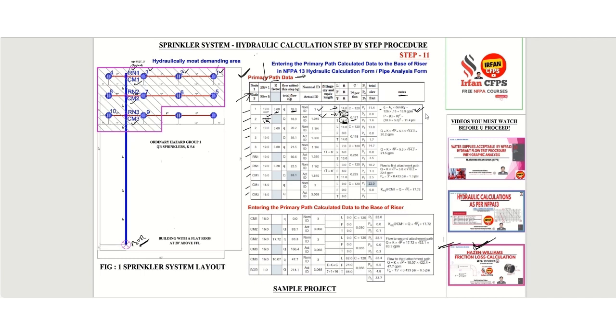The friction loss is 0.117 per foot using the Hazen-Williams formula. Multiplying this by the total length of 14 feet gives us the total friction loss Pf. Elevation is 0 since Nodes 1 and 2 are at the same height. The total pressure Pt is calculated using the pressure formula, and since this is the first sprinkler, the flow of 18.9 GPM is used.